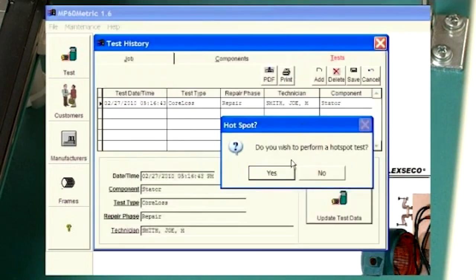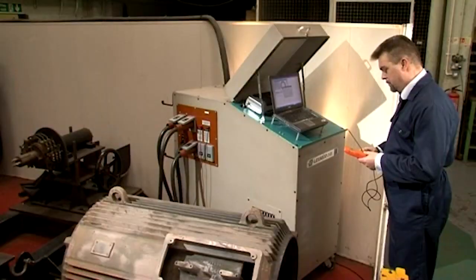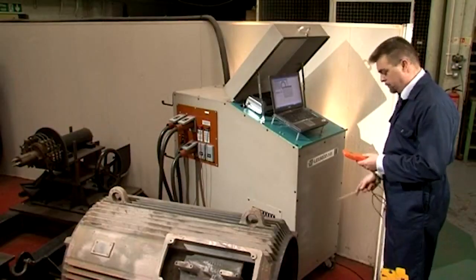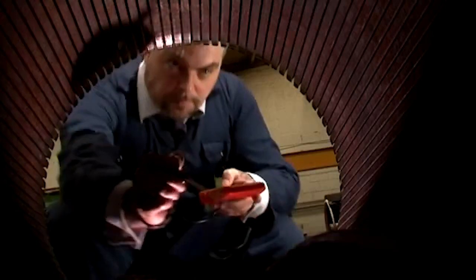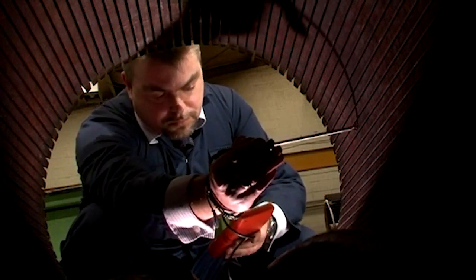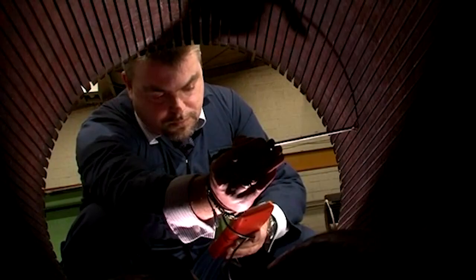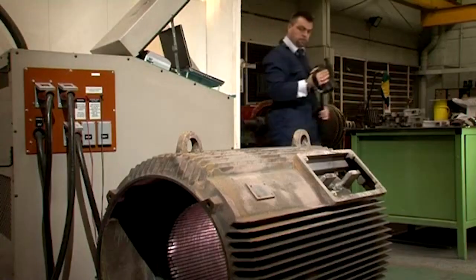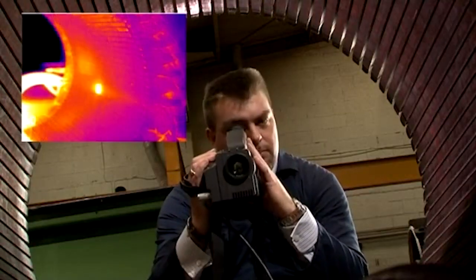LEXSECO core loss testing can then be applied to check for any localized areas of degradation, hot spots, once the test for average core loss has been carried out. This can be done in conjunction with a contact temperature probe, any suitable non-contact thermometer or a thermal imaging camera.